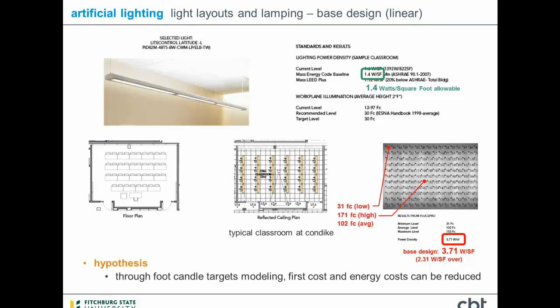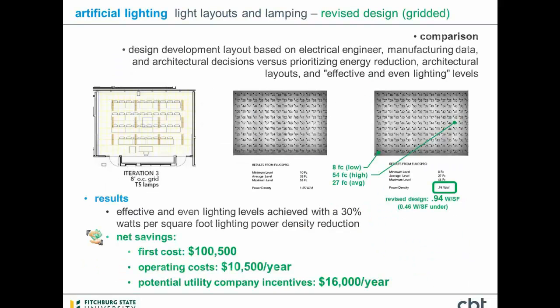We set a target for ourselves of trying to do 30% better than what we'd be allowed to do, and so we used the IES tools to go in and start going space by space and analyzing those. We ran a series of iterations for each one, and in the case of this conventional classroom, we worked out a more gridded arrangement of lights. We were able to hit the average right on the target, and bring the power density for that space down to just under 1 watt per square foot, which is even better than the code reduction limits we had initially set for ourselves.